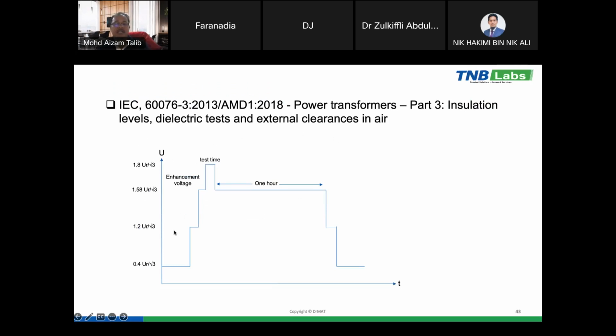Then this is the test sequence of the PD test on power transformers. We can see this is the applied voltage, and from this enhancement we see the level of the inception voltage. Then we pre-stress, and then we reduce the applied voltage and measure the extinction voltage. Then we sustain the voltage for up to 1 hour, and we measure the PD level for the power transformer. The PD level for 1 hour must be less than 300 picocoulomb.